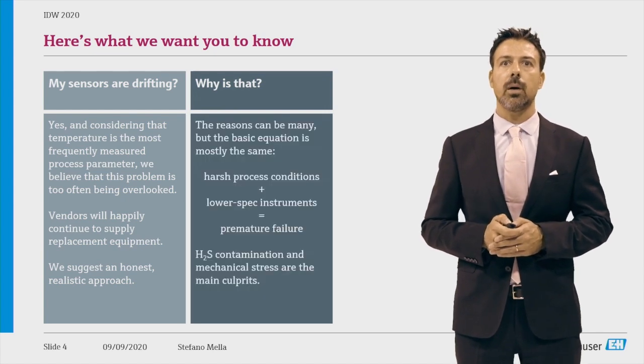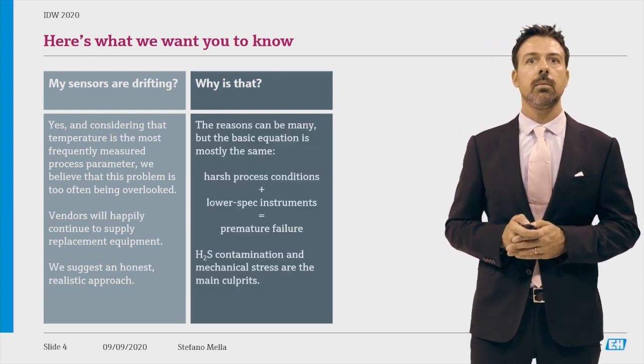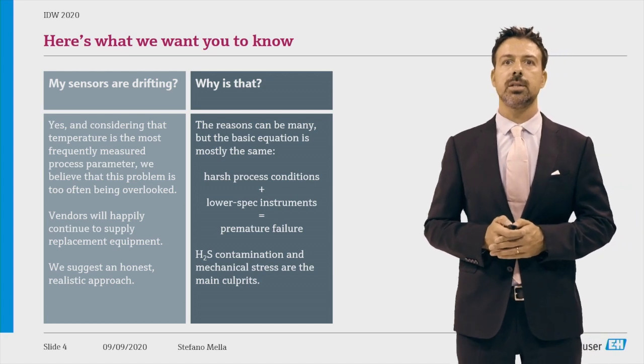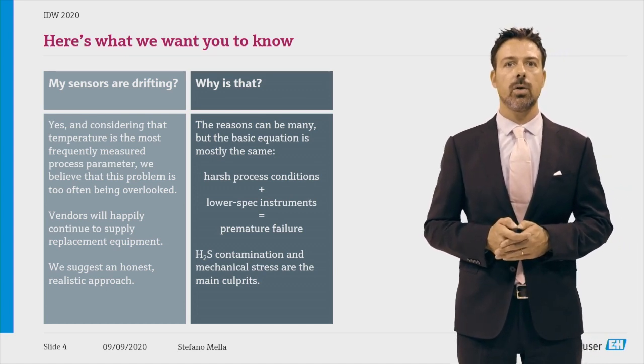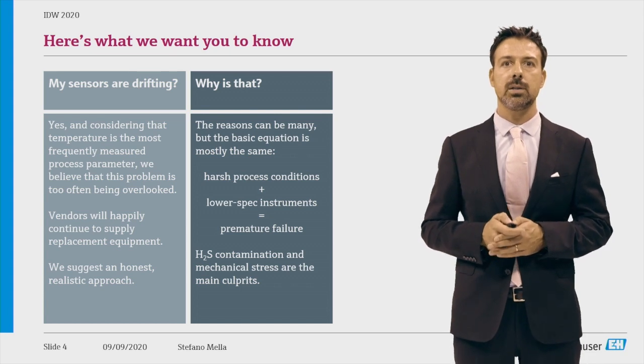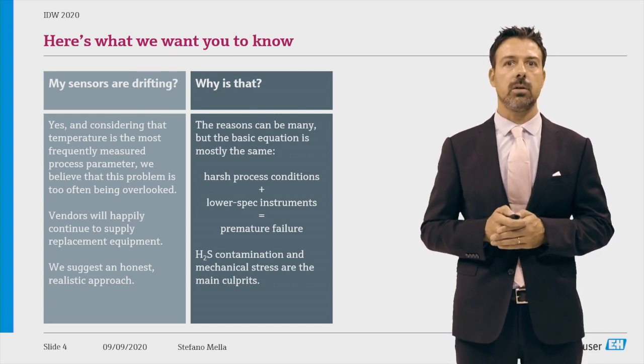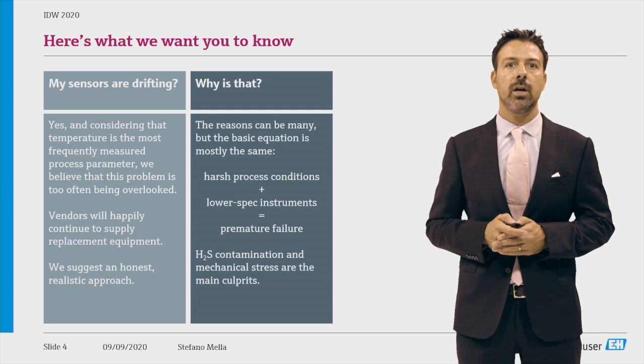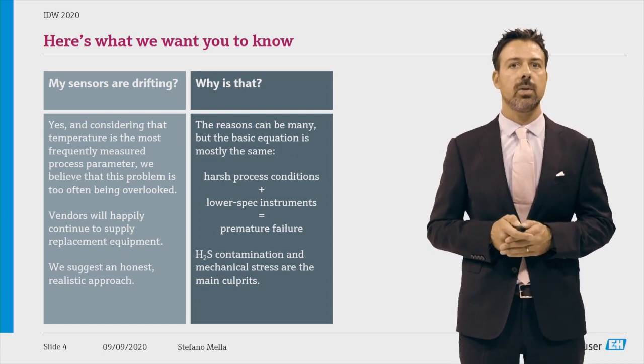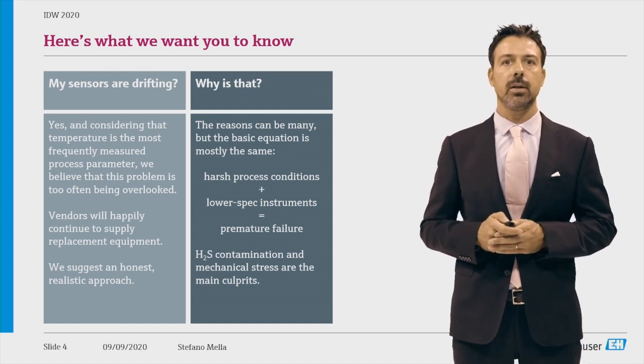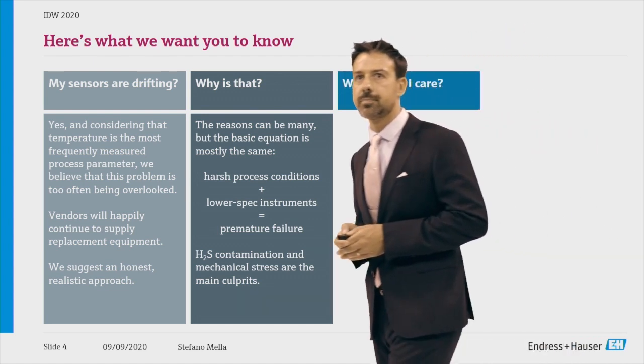Why do the thermocouples drift? The reasons can be many, but the basic equation is mostly the same. Critical conditions, together with lower spec instruments, lead to premature failures. And when we have H2S contamination and mechanical stresses on top, then the probability that they drift is even higher.